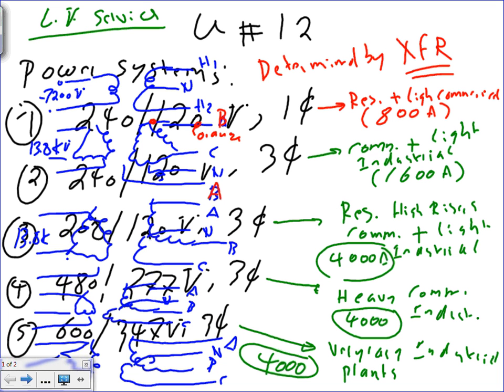Okay, so the advantage of this transformer, guys, center tap transformer, is where do you use it? Commercial plus light industrial. You can go all the way up to 1600 amps. You can go higher than that. Typically 1600 amps, 3-phase. Remember, 3-phase. If I want to add something to this, I would say if you have a load that is 10% or less single phase, this would be an ideal application for you. That's my rule: 10% or less single phase load in your building, meaning receptacles and lights. This is a good application where you can use a delta center tap.